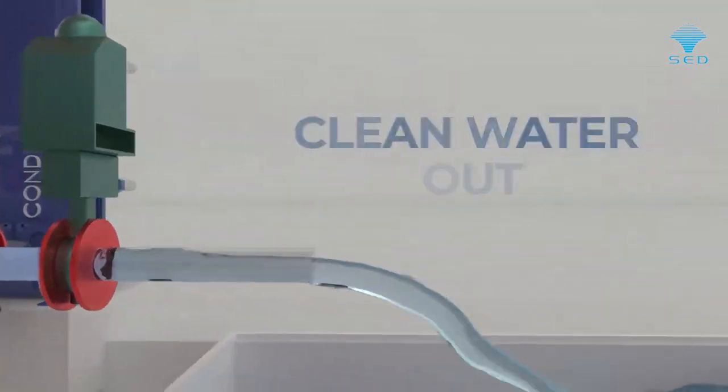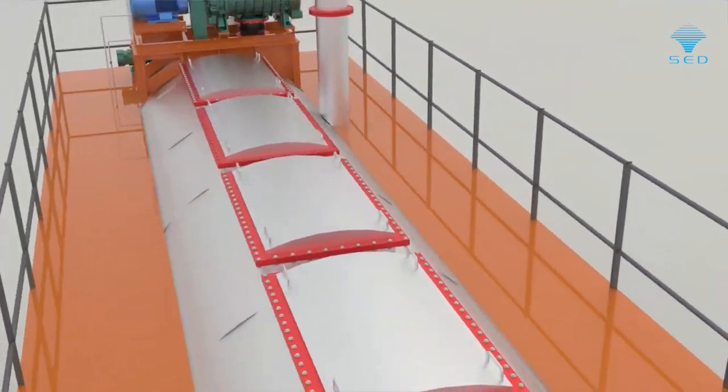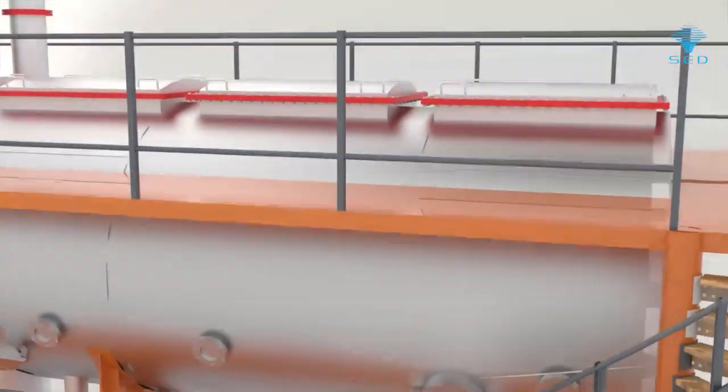The system is based on completely recycling of heat energy. Therefore, there is no need for cooling, heating, condensing, or a vacuum station. During the plate evaporation process, liquid is pumped between thin plates with the heating medium on the mating surfaces.